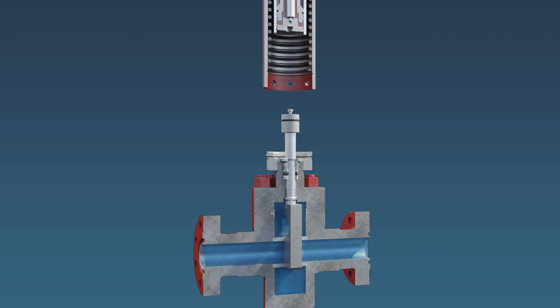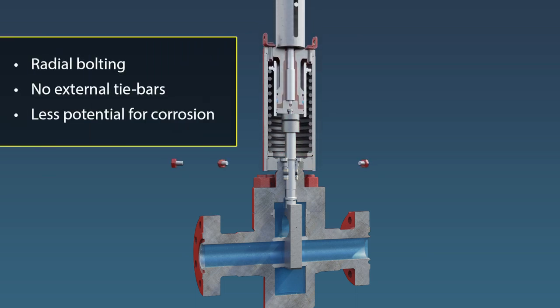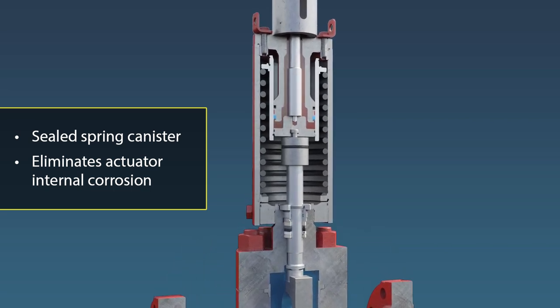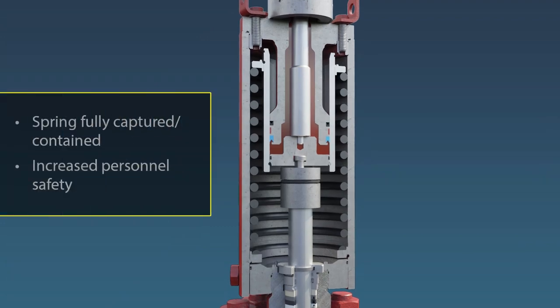The Streamflow reverse-acting SRA hydraulic actuator can be removed and installed independent of the gate valve and the bonnet assembly. The SRA hydraulic actuator is also designed with a non-pressurized steel spring canister, allowing the actuator's internal piston and cylinder to function within the canister, keeping personnel safe in the event of spring canister damage.